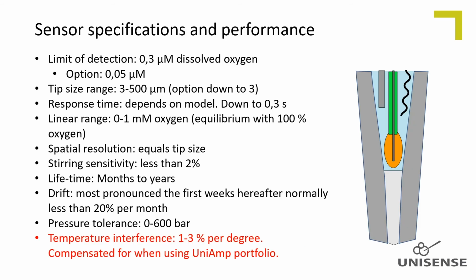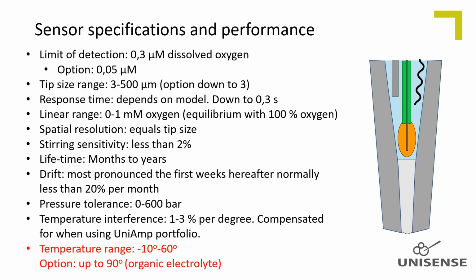electrolyte. In the web lecture about amperometric microsensors, the temperature influence is discussed in detail, and it is explained why temperature compensation is difficult for amperometric microsensors. The temperature interference is about 2% per degree. For sensors used with the new Unisense UniAmp portfolio, temperature is compensated for within a ±3 degrees Celsius interval. The sensors can be used from -10 to 60 degrees Celsius. For applications at higher temperatures, we produce sensors with organic electrolyte, which can stand higher temperatures.